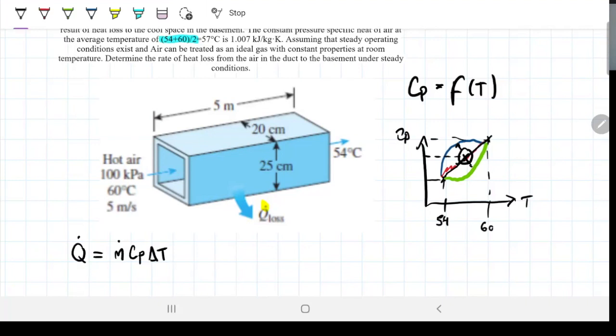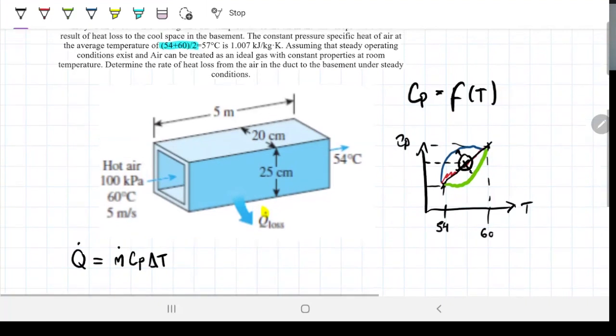Delta T, 60 minus 54, that's 6, easy. Cp, we've been given, that is 1.007, easy. The only thing we don't have is a mass flow rate. So if we find the mass flow rate for this problem, we've solved the problem. To find the mass flow rate, we're obviously going to use these conditions that are given here. Check out.